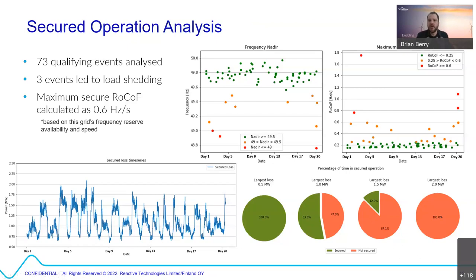What does this mean? Fundamentally, the people running the grid were saying our policy is to find out what your largest loss is, which is typically their generator, a 3 megawatt diesel generator. They said, as long as our frequency reserve is equal to 3 megawatts, our largest loss, we're golden. The answer to this is no, you're not golden, because even though you have that reserve, it's not fast enough to prevent the under-frequency load shedding.